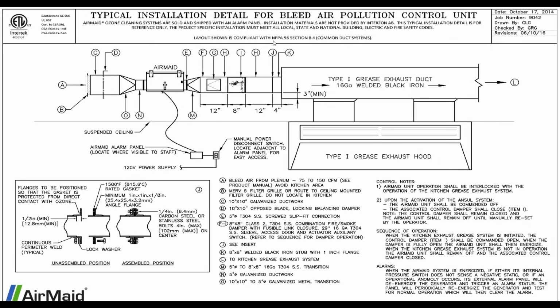This is all compliant with NFPA 96. This is all approved with all that. We'll actually ship out pretty much all of these connections with the AirMaid as well. But essentially, we have to have about 75 to 250 CFM, roughly in that range, depending on the size of the AirMaid. We have to have about that much airflow, what we call bleed airflow, coming across the AirMaid to grab those ozones and get sucked into the grease ductwork there.